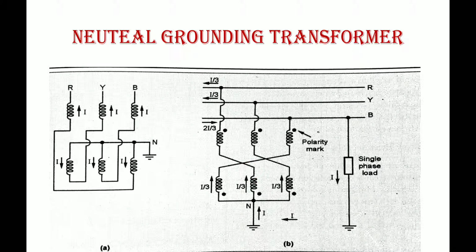If the currents are equal in all the windings, the neutral point stays fixed and the line to neutral voltages remain balanced, as they would be on a regular four-wire system. In practice, single phase loads are distributed as evenly as possible between the three phases and the neutral, so that in a balanced condition the unbalanced load current I will obviously be relatively very small.